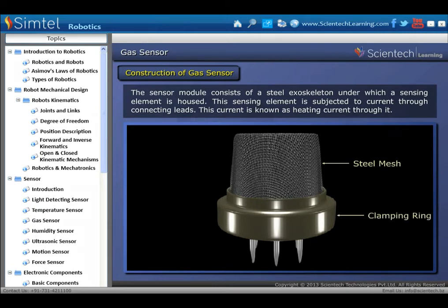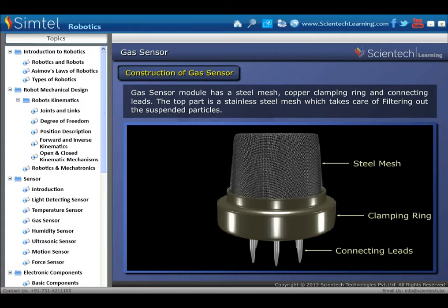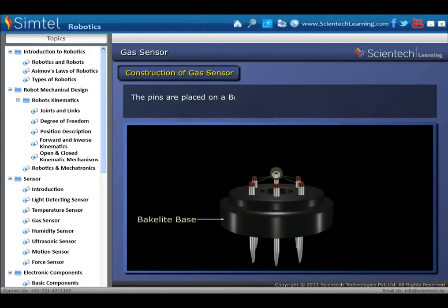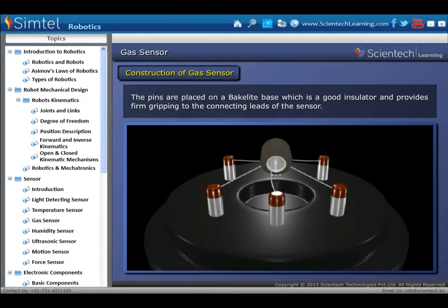Construction of gas sensor: the sensor module consists of a steel exoskeleton under which a sensing element is housed. This sensing element is subjected to current through connecting leads, known as heating current. The gas sensor module has a steel mesh, copper clamping ring, and connecting leads; the top part is a stainless steel mesh. The pins are placed on a bakelite base, which is a good insulator and provides firm gripping to the connecting leads of the sensor.